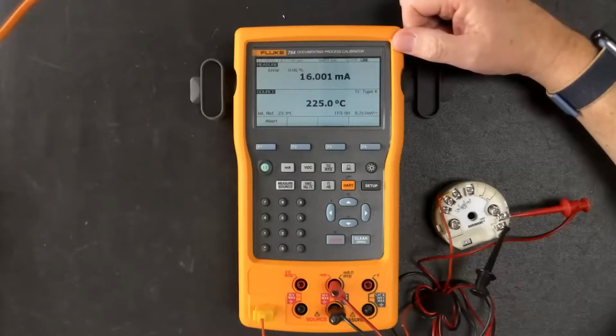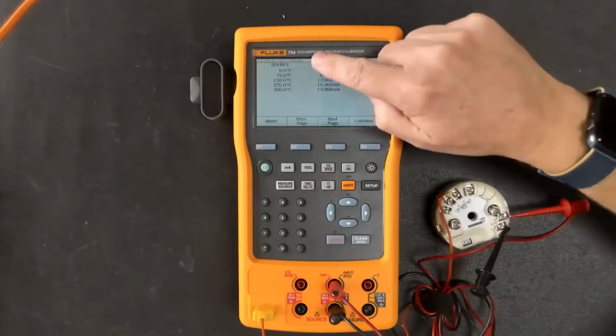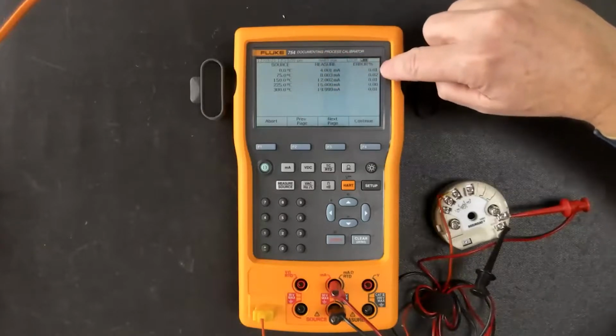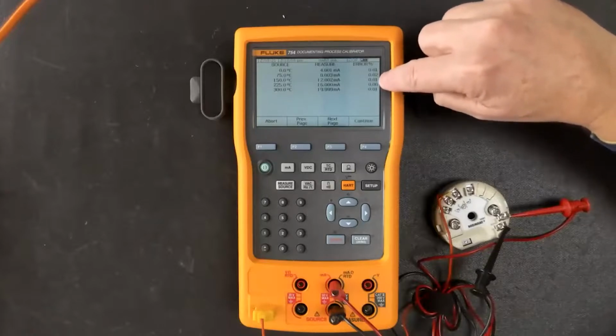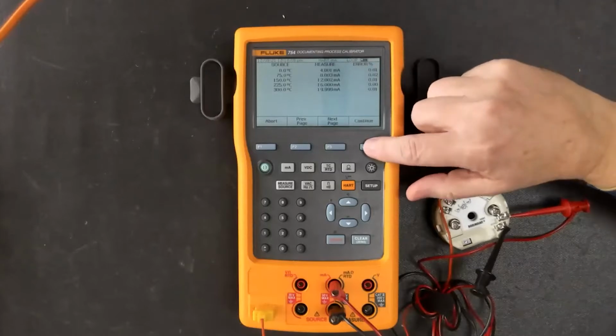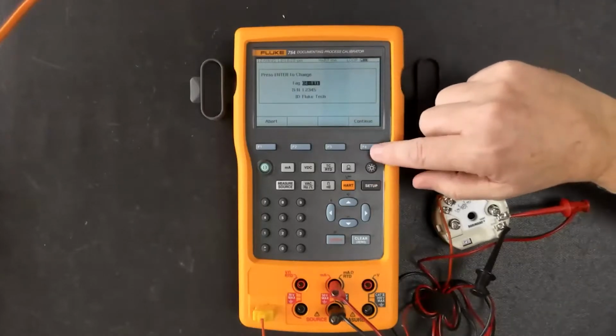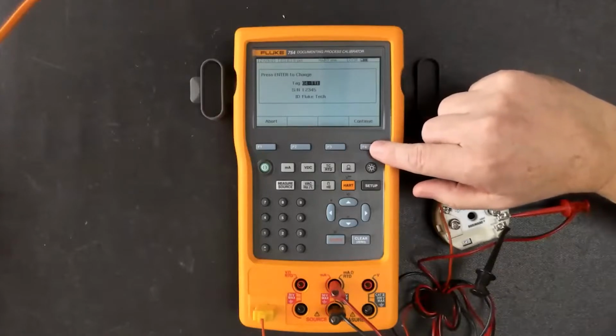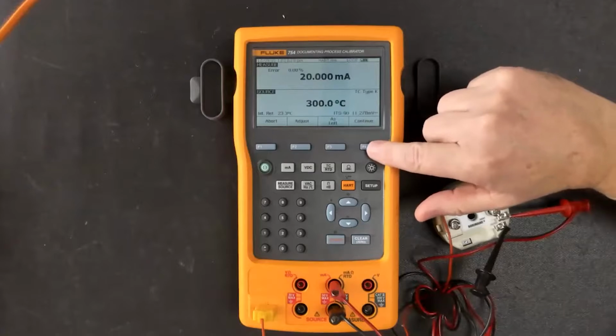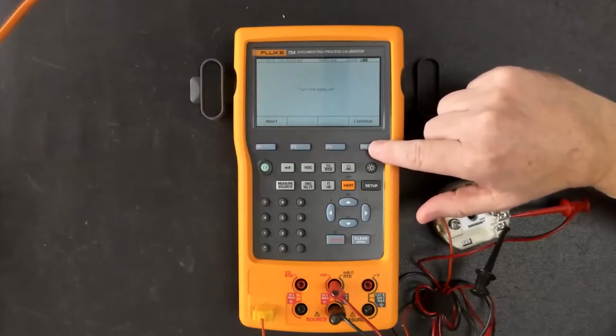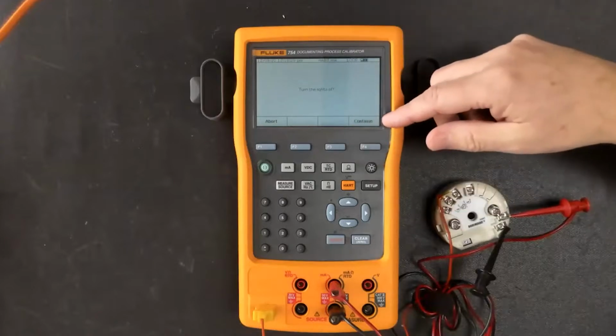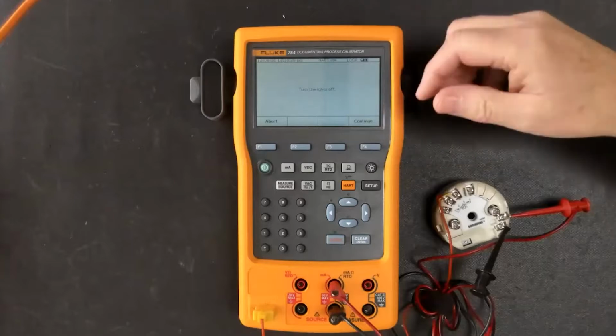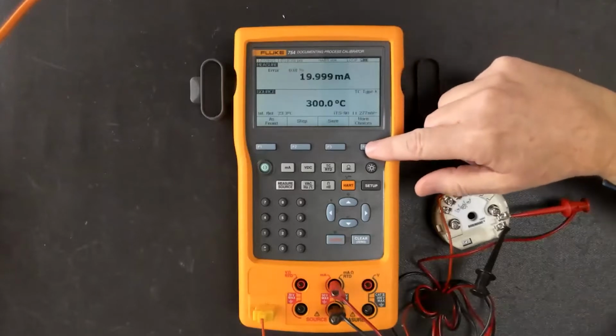And all this is important data, because this is what gets sent back up to the ProCal software and gets populated into the database. So as you notice now, we've completed our test, and wow, look at the error percentage now. We are pretty much right on the money. Okay, so we're well within the spec. We're in good shape here. We'll continue. Again, it's going to record that same data. The tag ID number, the SIL number, who did the test, and that's it. So we'll continue, and then it says, okay, the final message that can be put in. If there's a message for the tech, let's say to turn lights off or close the box, whatever, that's done.